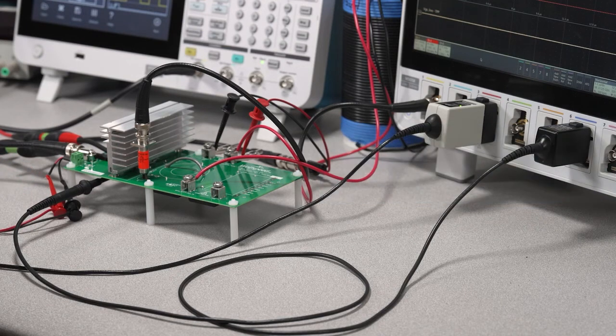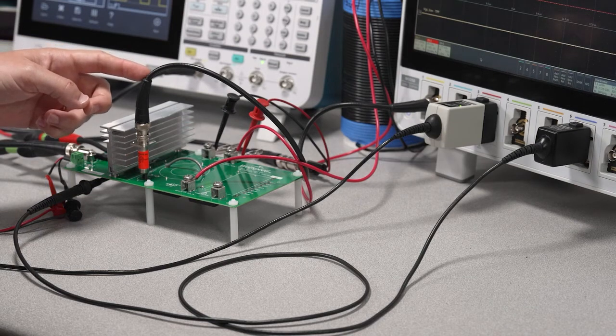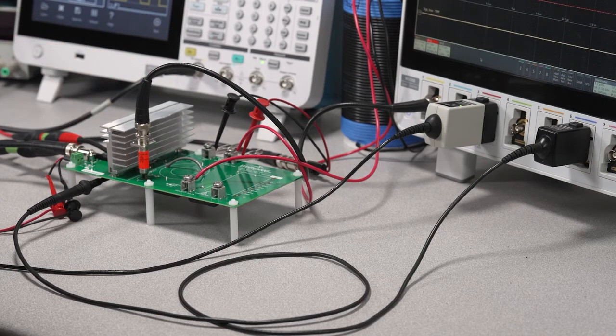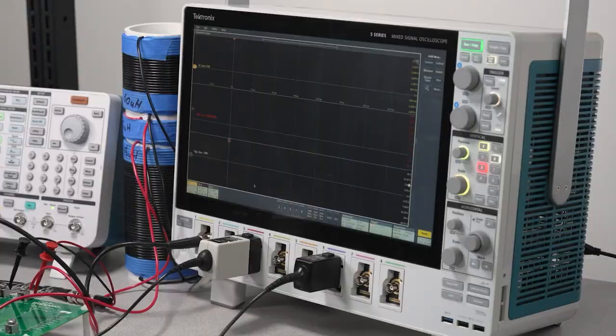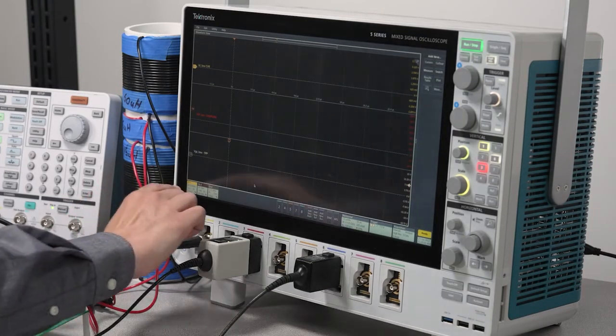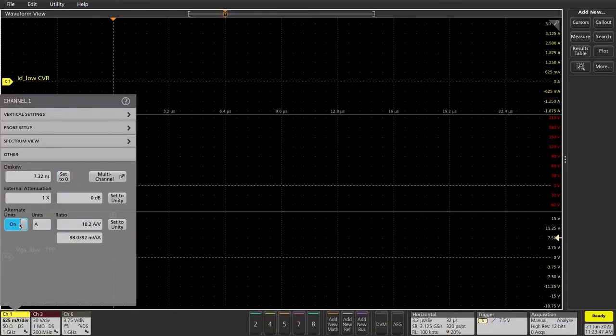As I noted before, for making the drain current measurement, I'm using a CVR connected to channel 1 with a 50 ohm BNC cable. Now I'll show you how to set up the measurements using the wide bandgap double pulse testing application. I'll set custom units on channel 1 to read current from the CVR.